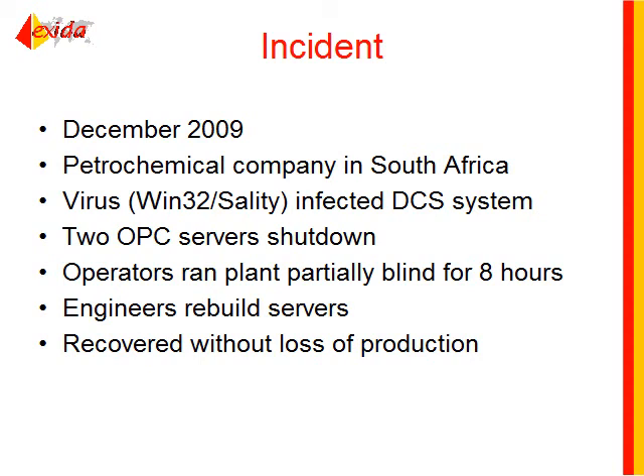They experienced a virus called the Sality virus. It got into the DCS system, very specifically into 2 OPC servers that were pretty critical to the communication throughout the system. I'll show you the system architecture in a minute, but the OPC servers were providing communications between the DCS and an electrical control system, and between the DCS and a safety system. So when these servers shut down, the operators were forced to run the plant partially blind for about 8 hours while the engineers were rebuilding the servers from scratch.